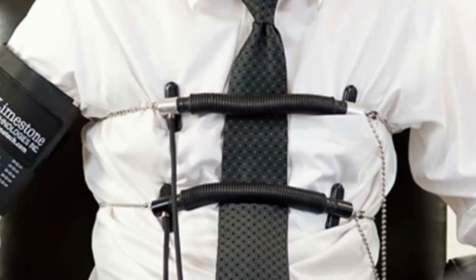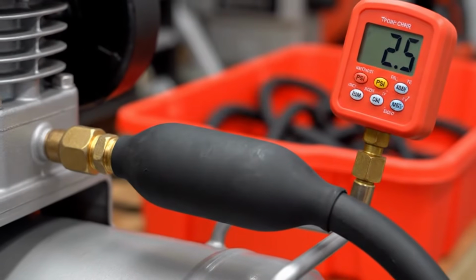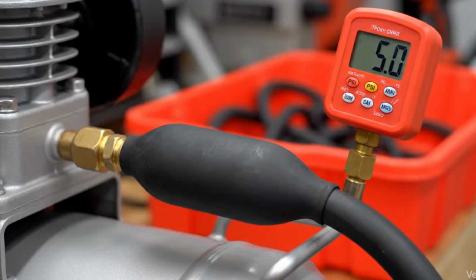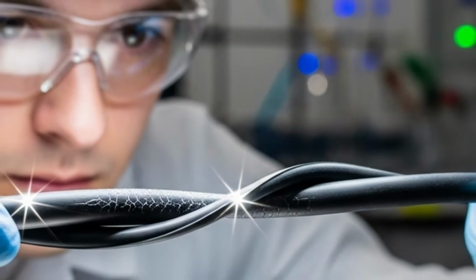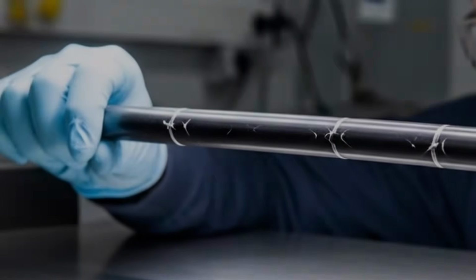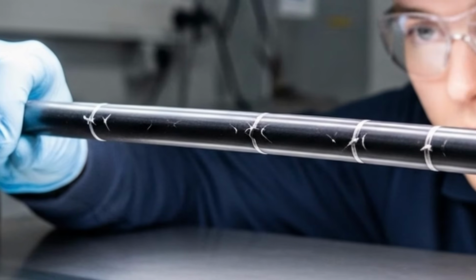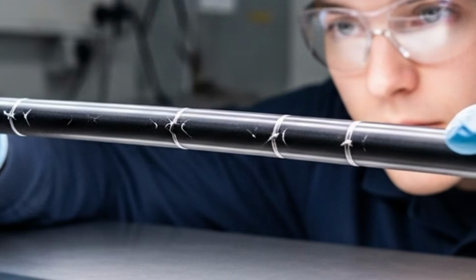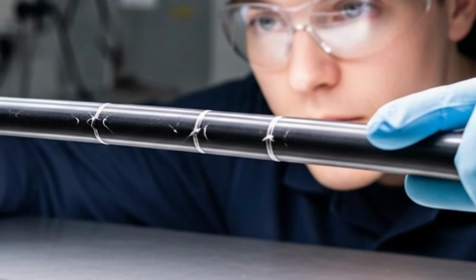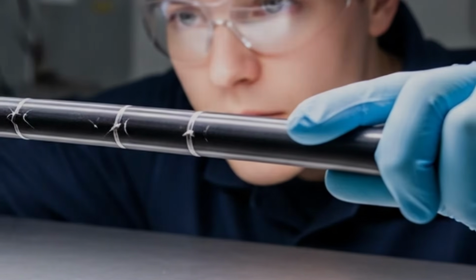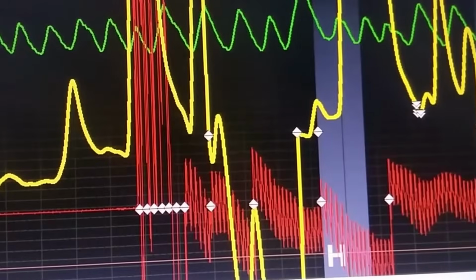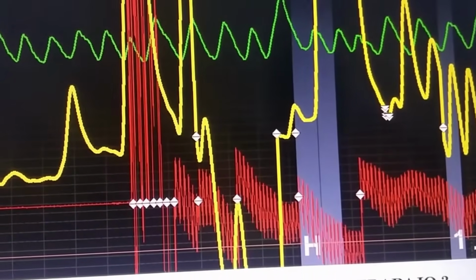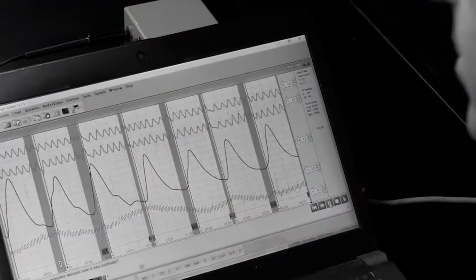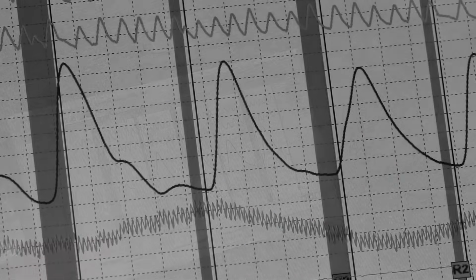Before approval, each tube goes through resistance tests, inflated with compressed air at different pressures to simulate deep, rapid, or shallow breathing. If even the slightest leak is detected, the tube is discarded. Technicians wearing protective glasses and gloves inspect each piece under LED lighting, making sure it can capture even the subtlest changes in breathing. This is no minor detail. The frequency and depth of air entering and leaving the lungs is one of the most sensitive indicators of stress.